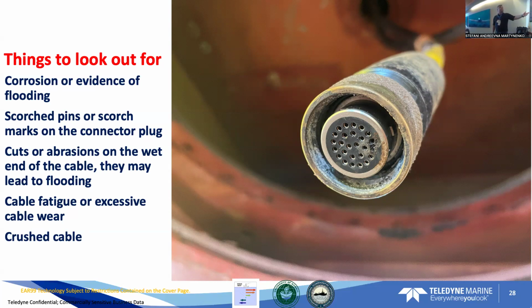So, things to look out for are corrosion and evidence of flooding, scorched pins or scorch marks on the connector plug, cuts, abrasions on the wet end of the cable. They may lead to flooding. Keep an eye out for cable fatigue or excessive cable wear and crushed cable. All pretty simple stuff.